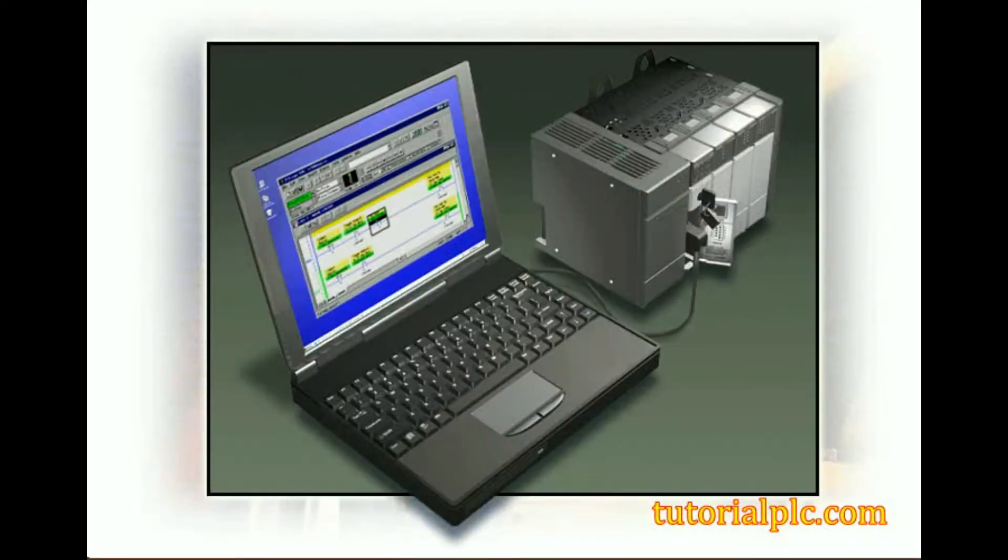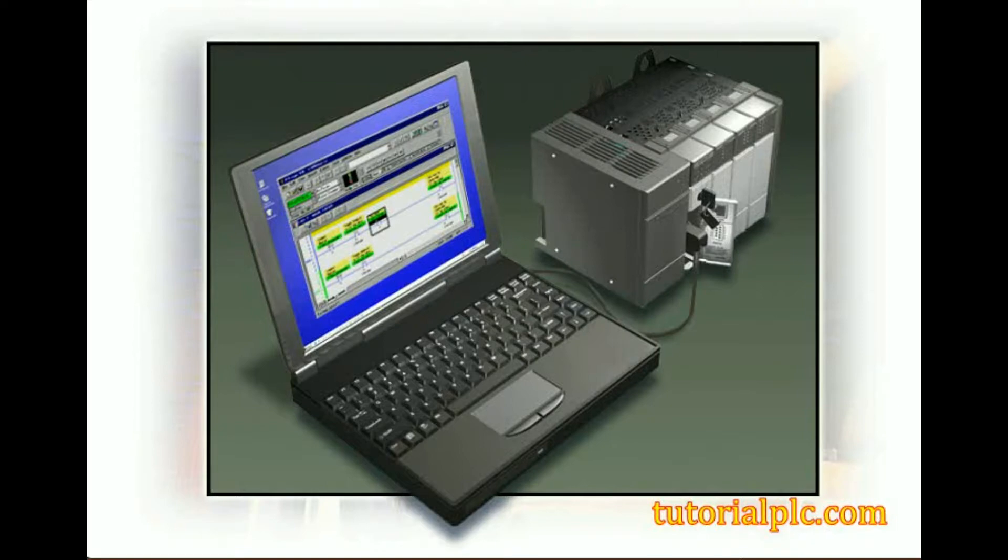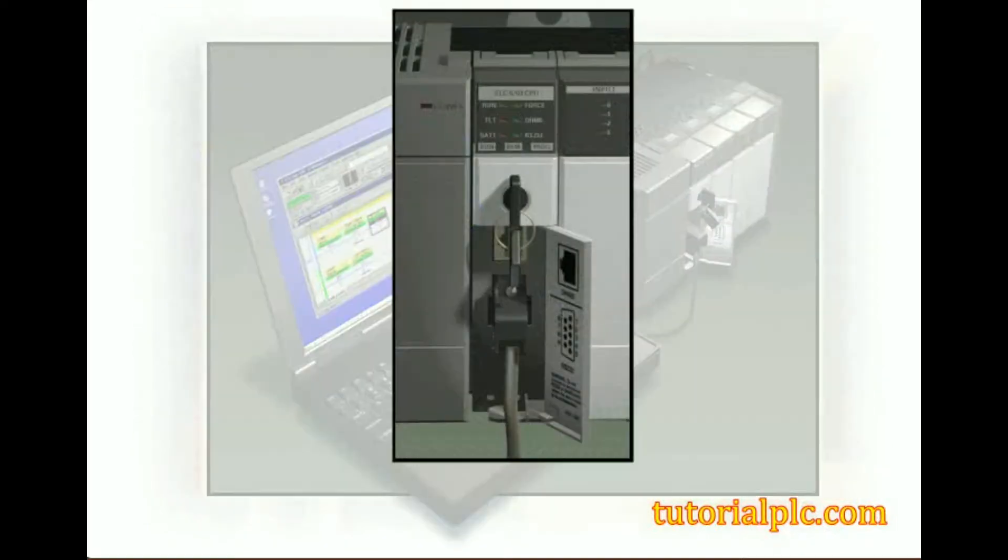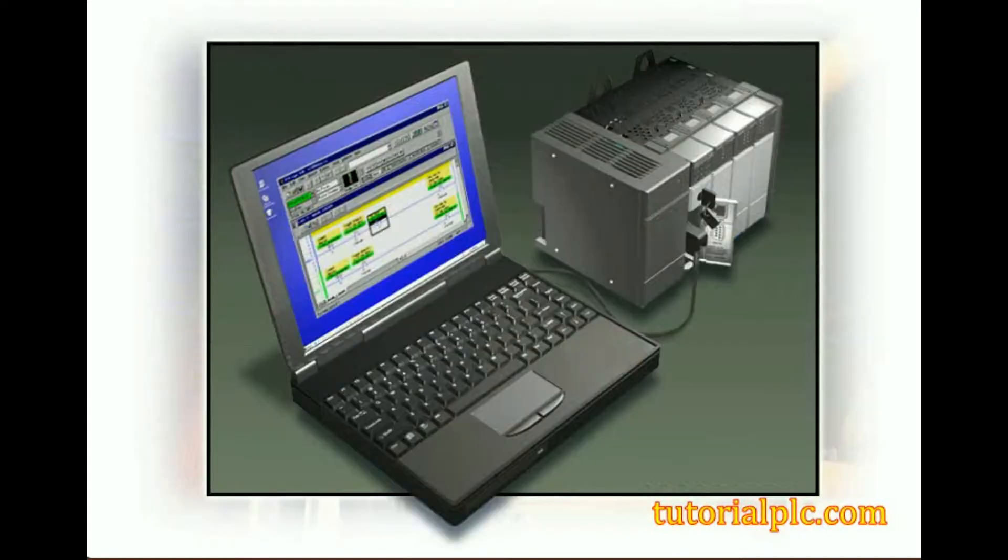Let's begin by looking at the hardware requirements for serial communications. With the SLC 5/03, 5/04, and 5/05 processors, a computer can directly connect to channel 0 on the processor via a standard RS-232 cable. This configuration provides for easy, direct communication with an SLC processor.